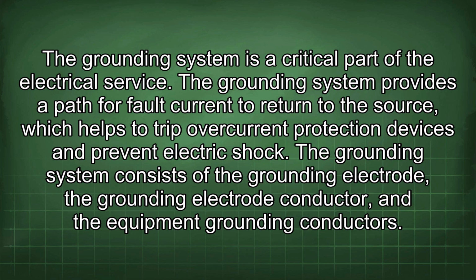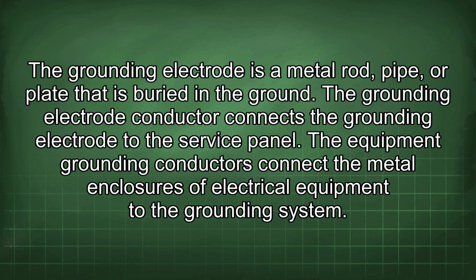The grounding system consists of the grounding electrode, the grounding electrode conductor, and the equipment grounding conductors. The grounding electrode is a metal rod, pipe, or plate that is buried in the ground. The grounding electrode conductor connects the grounding electrode to the service panel. The equipment grounding conductors connect the metal enclosures of electrical equipment to the grounding system.